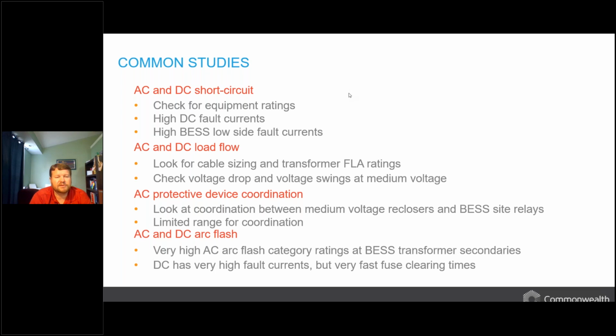We also look at voltage drop. We want to make sure that the requirements from the buyer are going to be met. So if you have too long of a cable, you may have excessive voltage drop, and we may need to do some upsizing because of that. Another common study is protective device coordination.